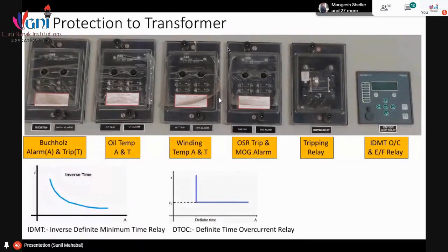Another one is DTOC, the definite time overcurrent relay. It will take the same time to trip irrespective of the rise in current. So if you set it at a particular amperage, then it will sense it and trip in the same timing.